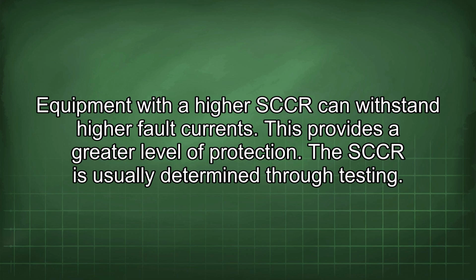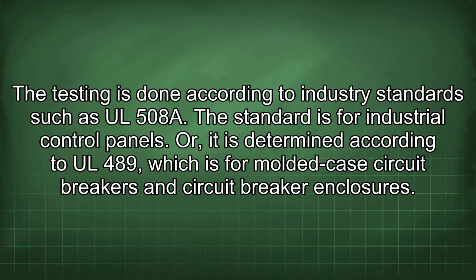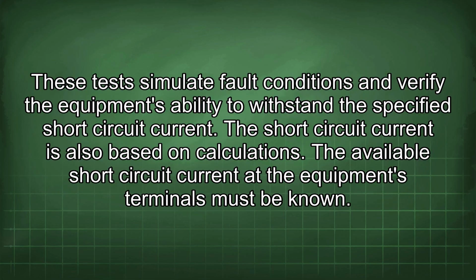The SCCR is usually determined through testing. Testing is done according to industry standards such as UL 508A, which is the standard for industrial control panels, or it is determined according to UL 489, which is for molded case circuit breakers and circuit breaker enclosures. These tests simulate fault conditions and verify the equipment's ability to withstand the specified short-circuit current. The short-circuit current is also based on calculations. The available short-circuit current at the equipment's terminals must be known.